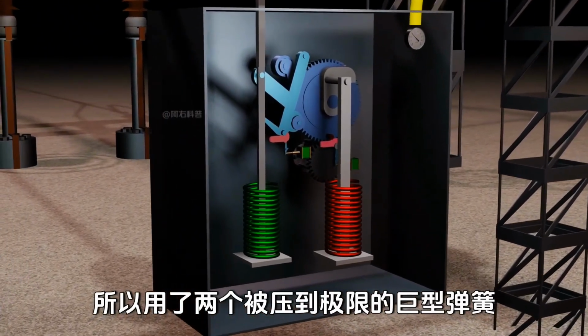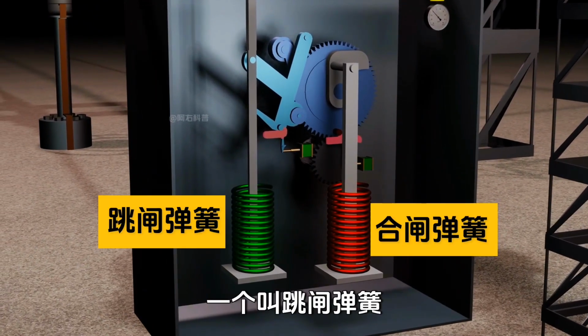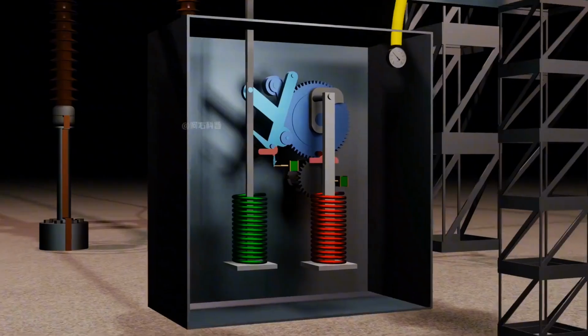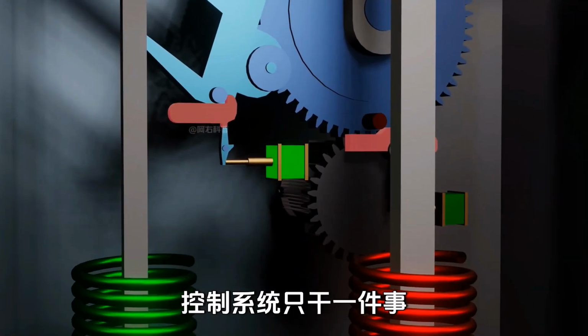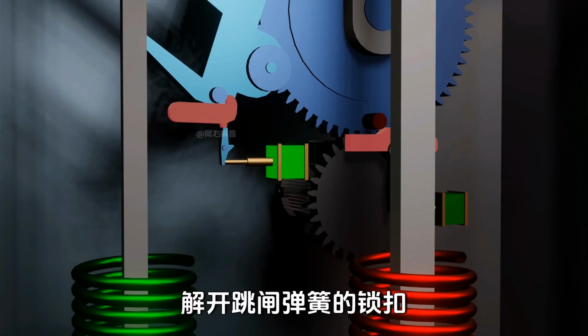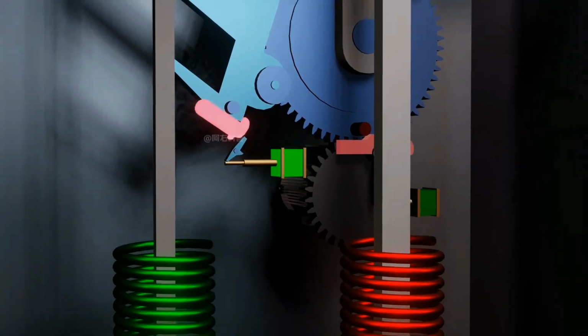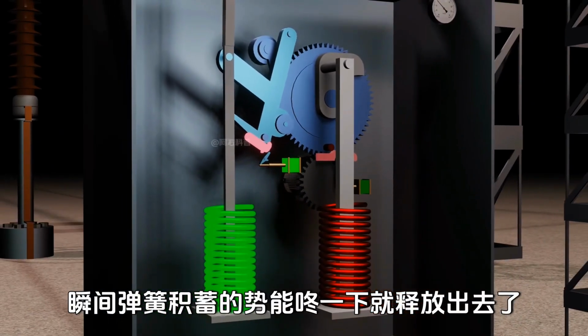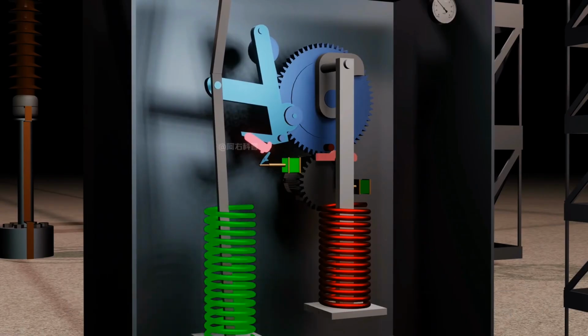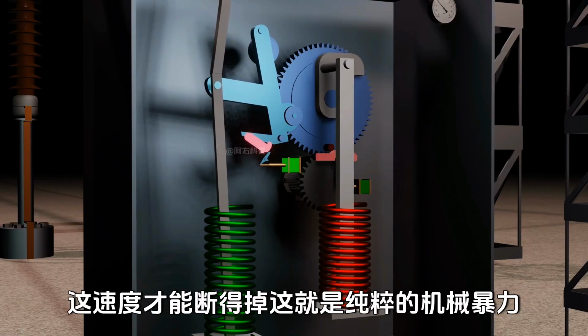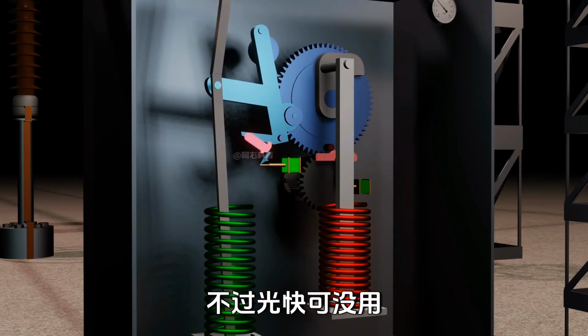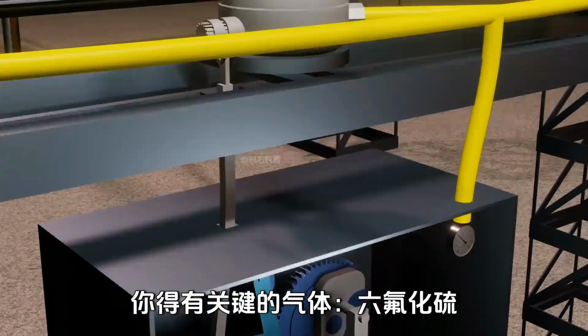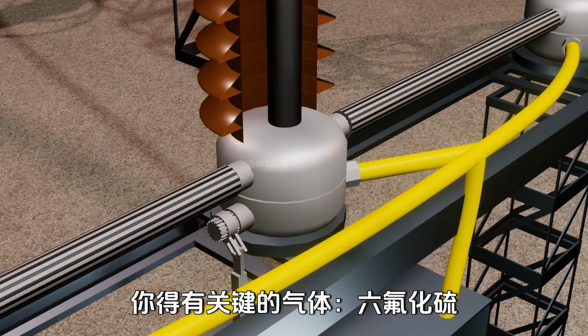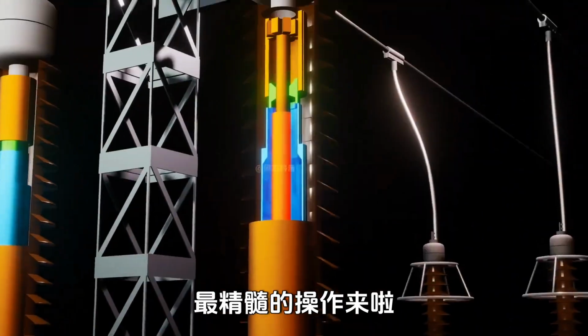So the breaker uses two heavy springs, one called the trip spring and the other the closing spring. When a control signal arrives, the system does only one thing. It releases the lock on the trip spring. In an instant, all the energy stored in that spring bursts out, creating a powerful mechanical force. But speed alone isn't enough. Here's where sulfur hexafluoride gas, or SF6, plays its key role.